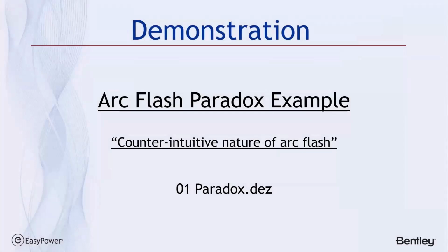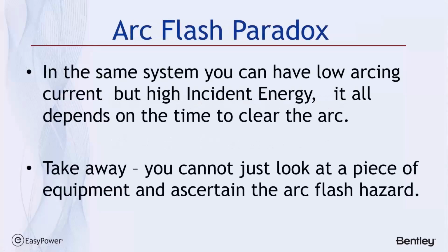It describes the counterintuitive nature of arc flash. And what it really means is, in the same system, you can have low arcing current but high incident energy. It all depends on the time to clear the arc. So the takeaway that I want to make sure you're left with is you cannot just look at a piece of equipment and ascertain the arc flash hazards in the system.